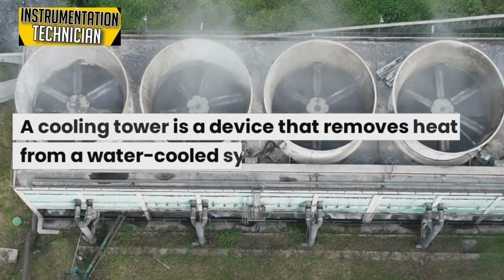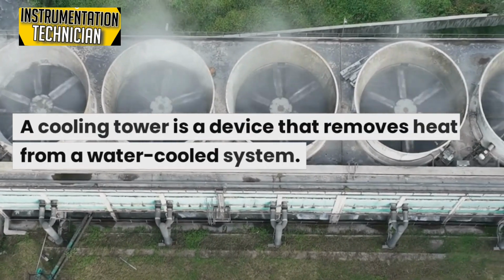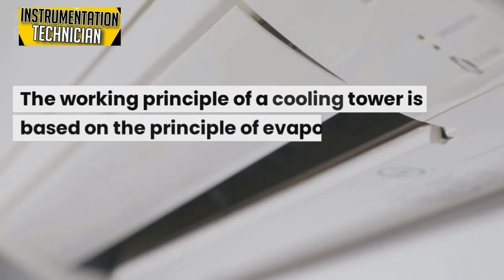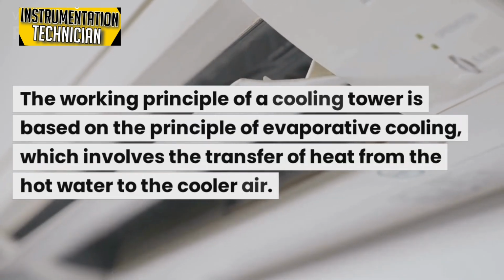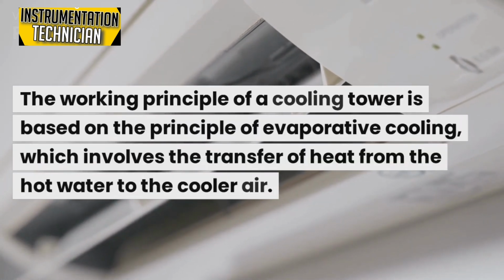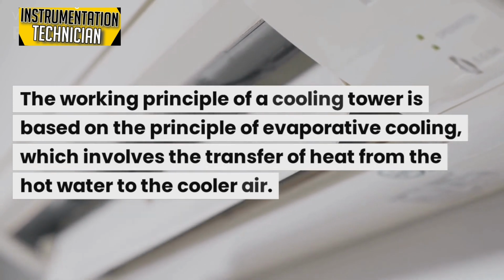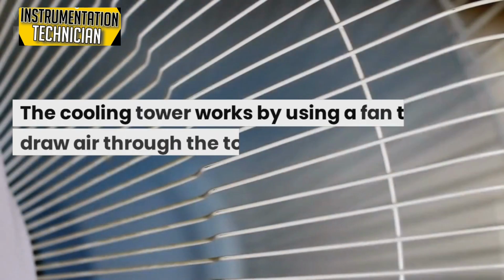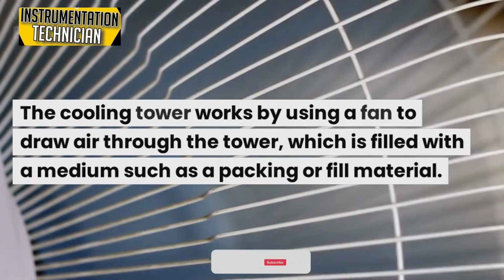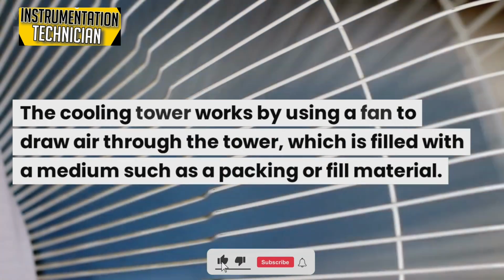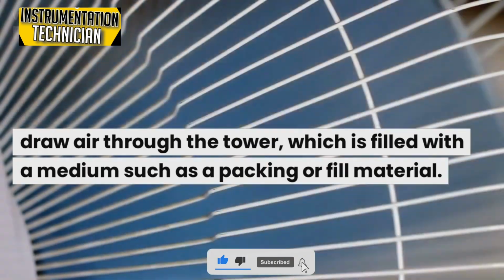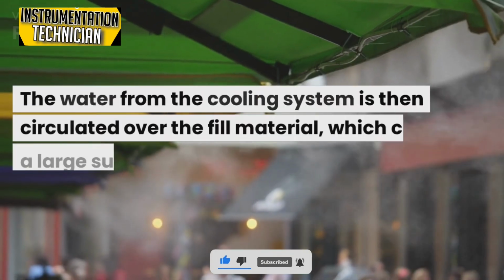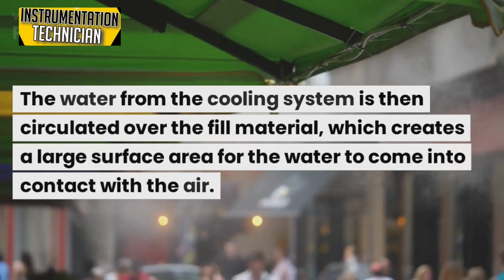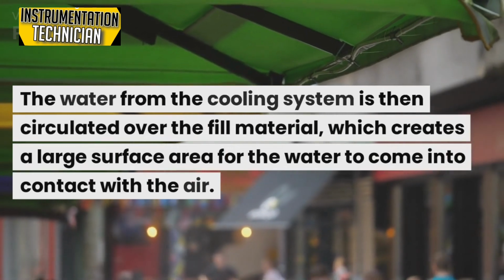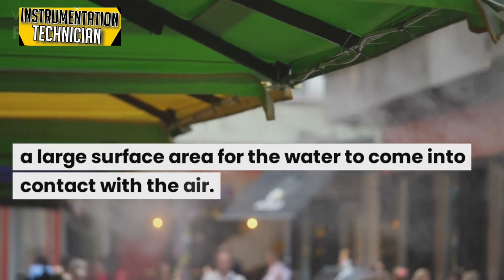A cooling tower is a device that removes heat from a water-cooled system. The working principle of a cooling tower is based on the principle of evaporative cooling, which involves the transfer of heat from the hot water to the cooler air. The cooling tower works by using a fan to draw air through the tower, which is filled with a medium such as a packing or fill material. The water from the cooling system is then circulated over the fill material, which creates a large surface area for the water to come into contact with the air.